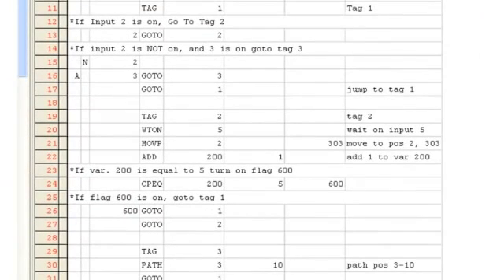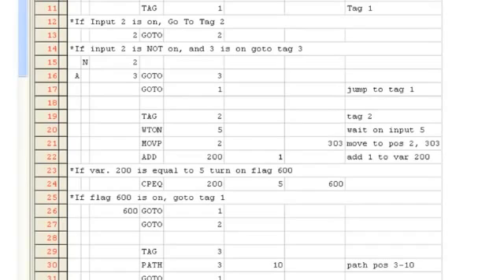The program will start at tag 1. If input 2 is on, we will jump down to tag 2. If input 2 is not on, we will skip that line. If input 2 is not on and input 3 is on, we will jump down to tag 3. If neither of these conditions are true, we will jump back up to tag 1 and try again.